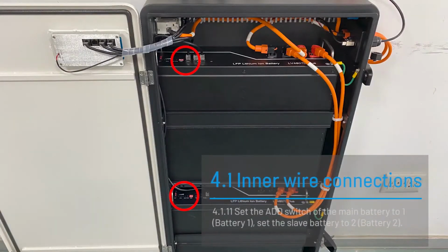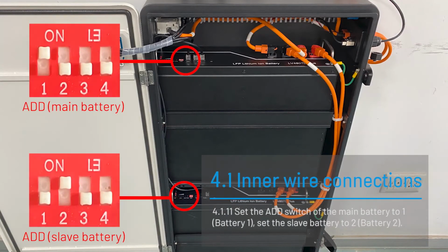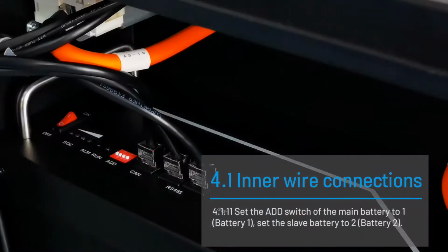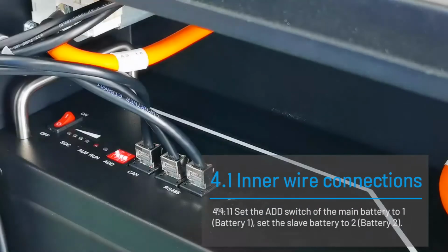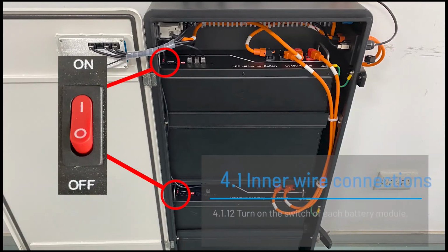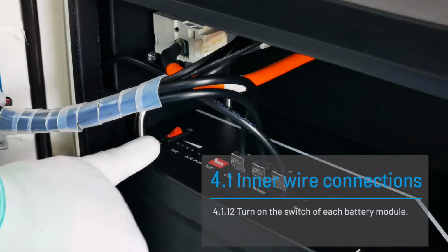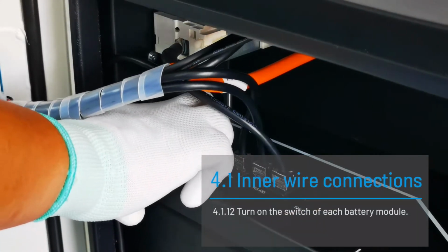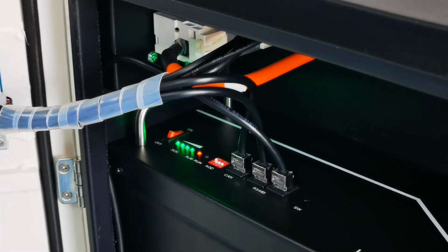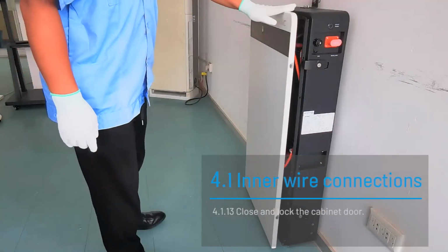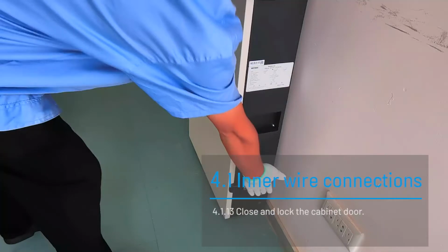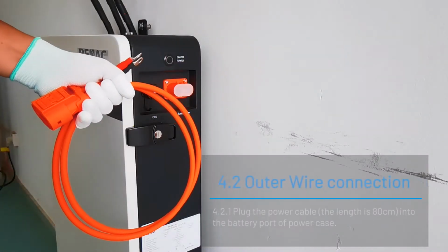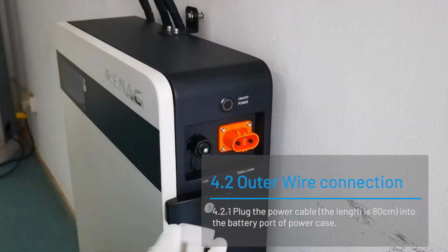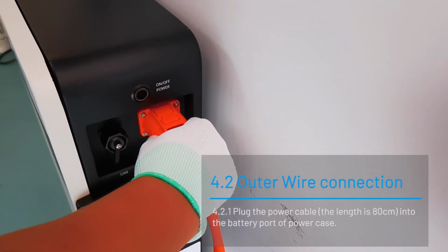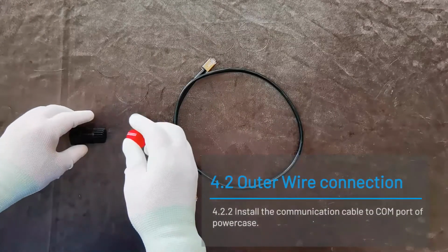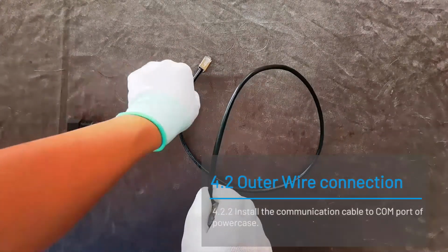Set the ADD switch of the main battery to 1, battery 1. Set the slave battery to 2, battery 2. Turn on the switch of each battery module. Close and lock the cabinet door. Outer wire connection. Plug the power cable into the battery port of the power case. Install the communication cable to the COM port of the power case.